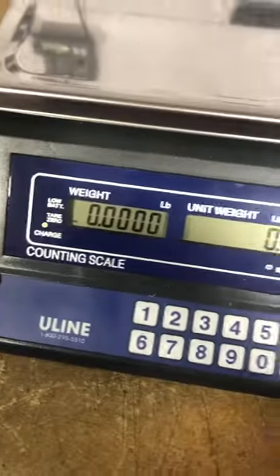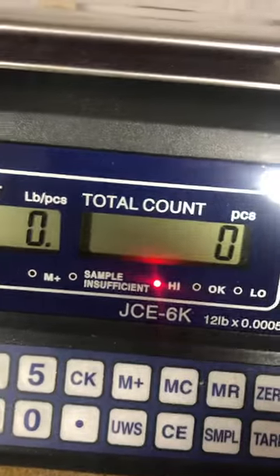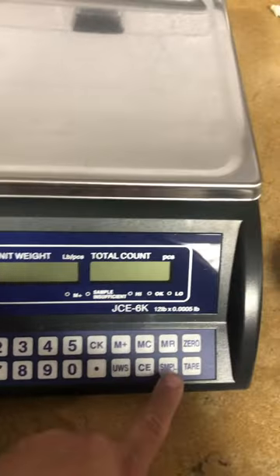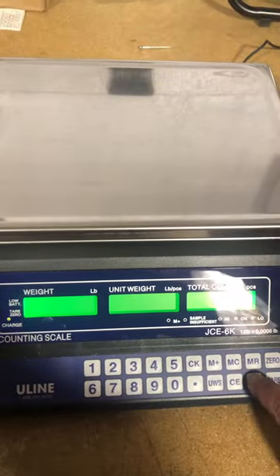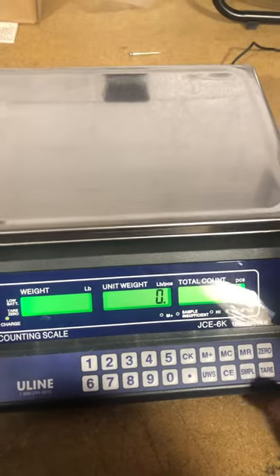This is a calibration adjustment of a Uline JCE-6K. Basically, you have to power down and hold the sample key at the same time you're powering it up. So you're going to hold the sample key down, power it up, and continue to hold it.